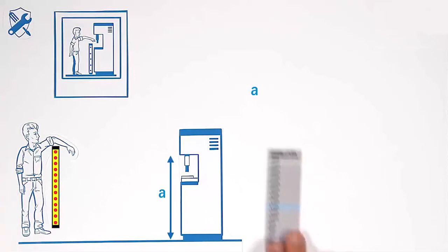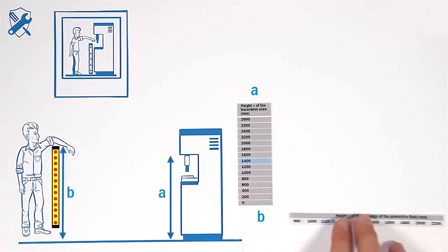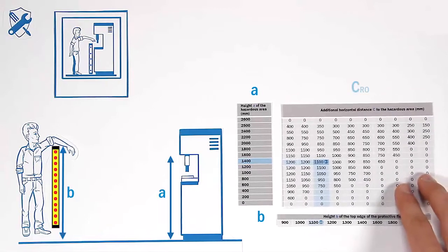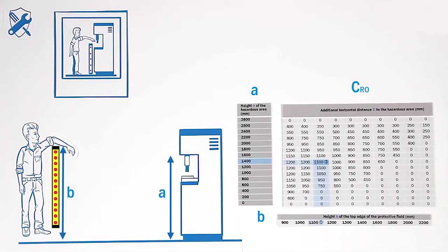To check a reaching over situation, the height A of the hazardous area and the height B of the upper edge of the detection zone are relevant. With the given values, the additional intrusion distance C reaching over can be identified on the table.